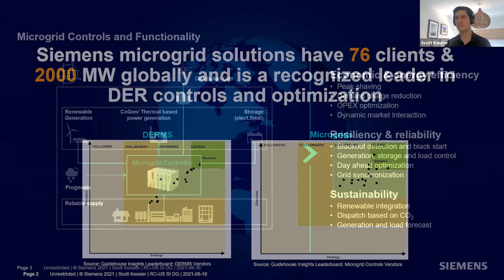So what is a microgrid controller and why is it important? The best way to think about a microgrid is that all of the individual components, whether that is the natural gas generators, the PV, the storage, what have you, all of those will have their own primary control system related to that device. It can receive commands, but it essentially tells whichever DER you're talking to what set points to hit.